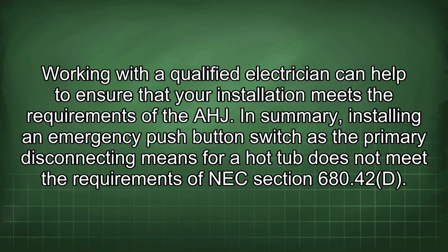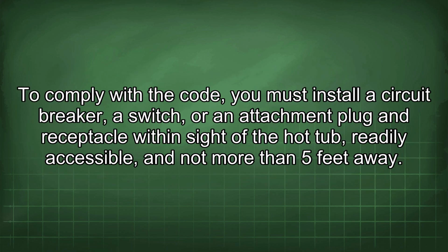In summary, installing an emergency push-button switch as the primary disconnecting means for a hot tub does not meet the requirements of NEC section 680.42(D). To comply with the code, you must install a circuit breaker, a switch, or an attachment plug and receptacle within sight of the hot tub, readily accessible, and not more than 5 feet away.